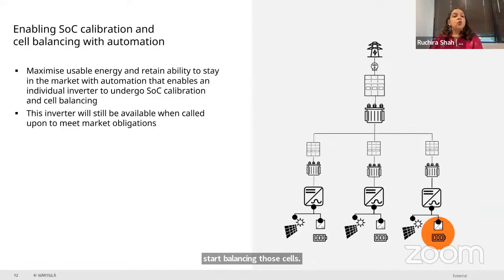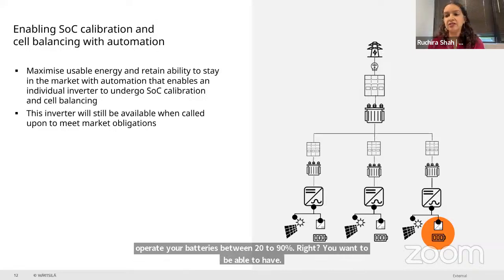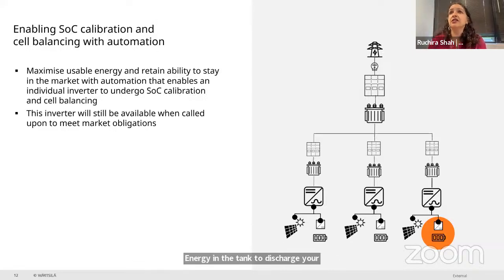We want to help our customers enable SOC calibration and cell balancing with automation. One challenge is that in normal operation, you typically want to operate your batteries between 20 to 90%, so you have energy to discharge as needed and to charge as needed to support ancillary service events. Most of our customers prefer to keep their batteries in that range.